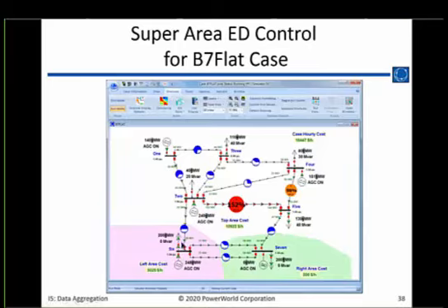So if you just kind of visually inspect the one-line diagram, you can see that we're actually exporting power from area left because it just has one generator, one load, and they're not matched. So it's exporting 48 megawatts somewhere. This guy's importing 200 megawatts, so the rest is coming out of here.